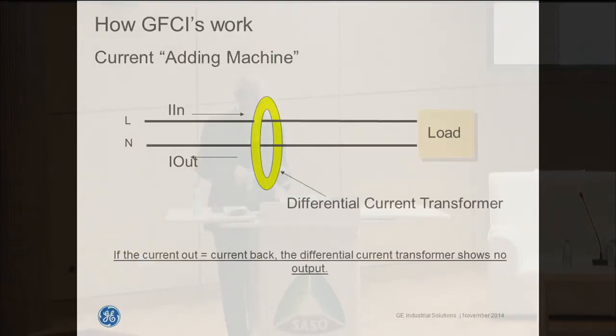This may be a little bit technical, but I want to talk about how ground fault circuit interrupters work. They basically look for current flow in a circuit, and they measure the amount of current that goes out to a load and check that the amount of current coming back through the neutral wires is exactly the same level. They're very sensitive, using a differential current transformer, a sensor, to understand that there may or may not be any loss of current in some place in the system.